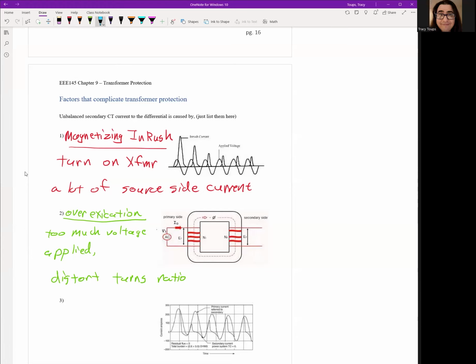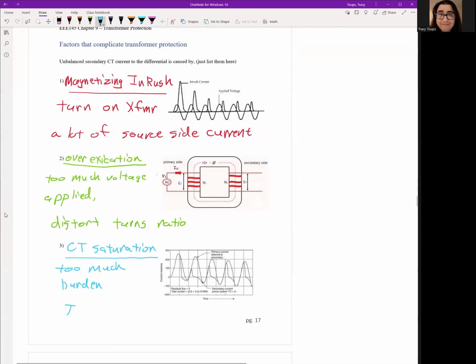All right, the last one is called CT saturation. So this is not necessarily the actual transformer itself, but the secondary instrumentation transformer, the current transformer itself can saturate. This is when you have too much burden. Remember, burden is how much impedance we put on the secondary circuit of this CT. When we have increased current, the increased current will cause more burden. And if we either improperly size the burden, or if the CTs are not made perfectly equal, meaning one manufacturer might make it different from others, one CT could go into saturation quicker than another CT, and then you'll get some problems because you'll get incorrect CT readings.